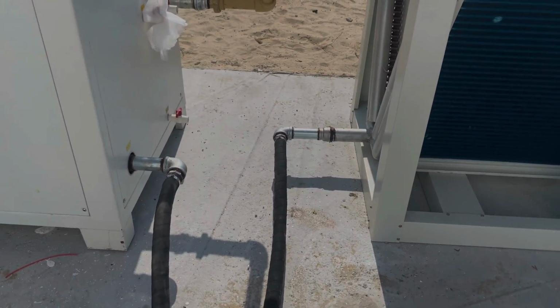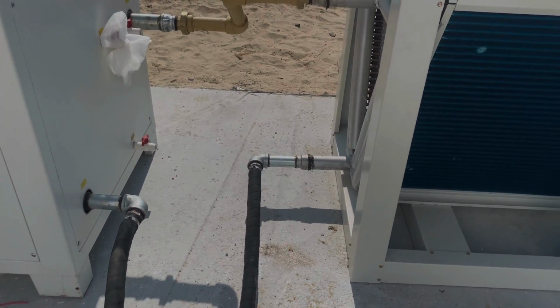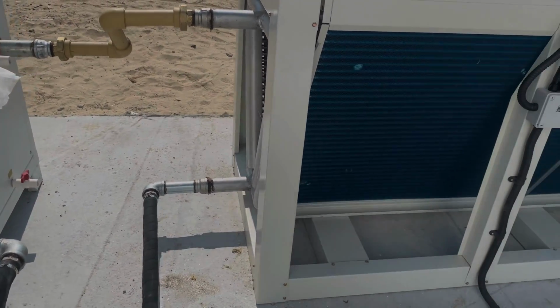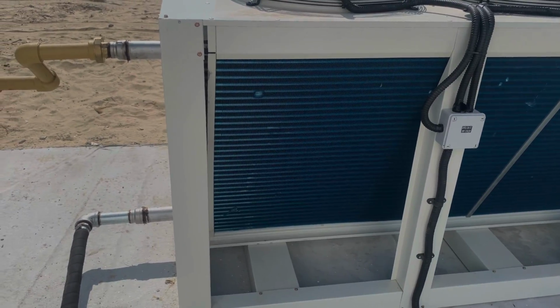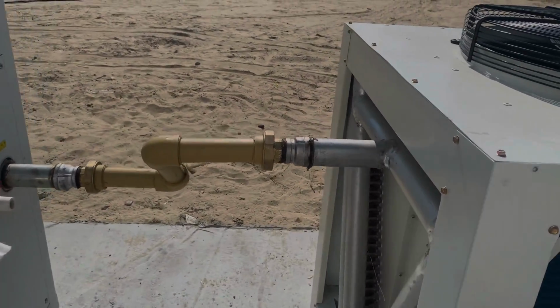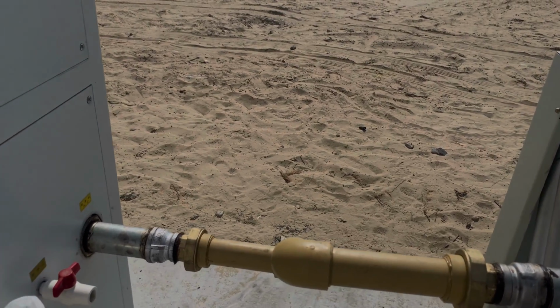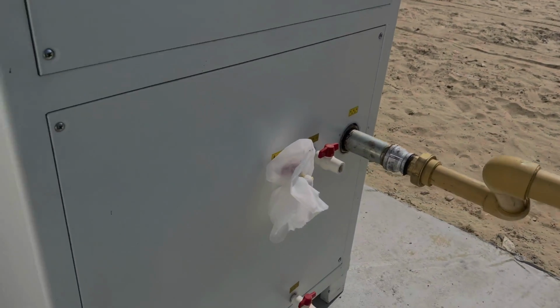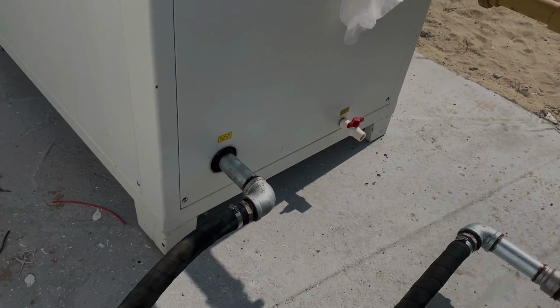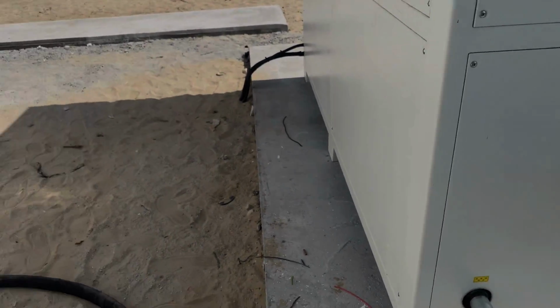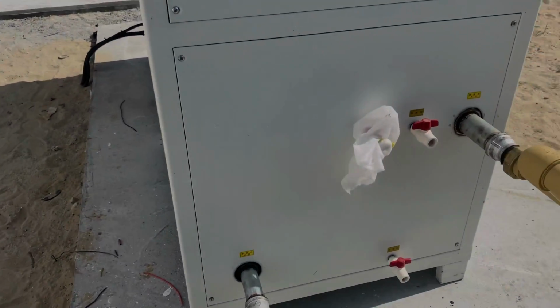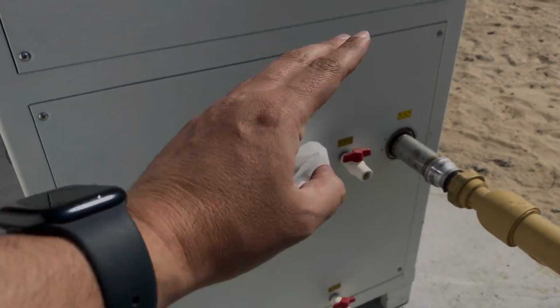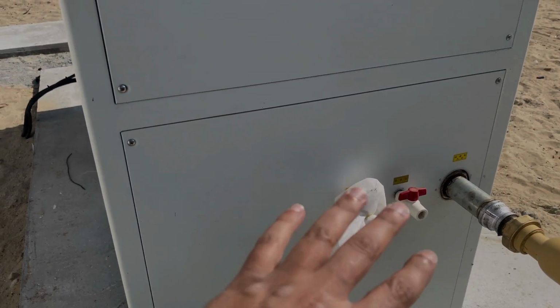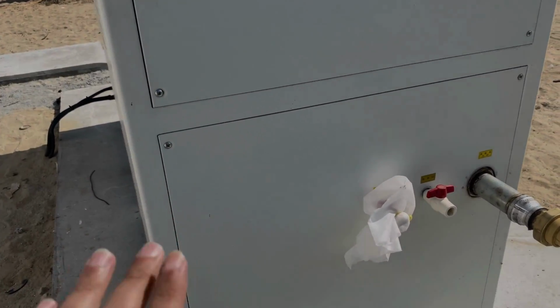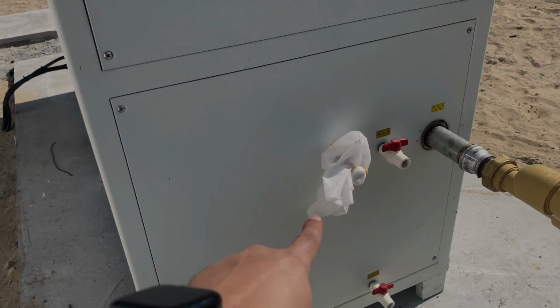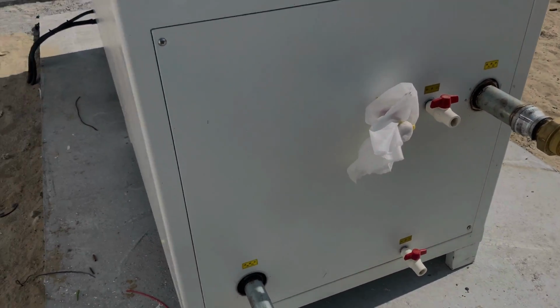What we did here is we have the outlet from the system going to the dry cooler first. The dry cooler will take most of the heat, and then from there it will go into the inlet for the chiller, and then from the chiller we have the outlet going back to the miner room here. The chiller has its own water supply, so you fill up the whole system with water or liquid, whatever you want. You have an overflow valve over there, and then the draining valve down there.